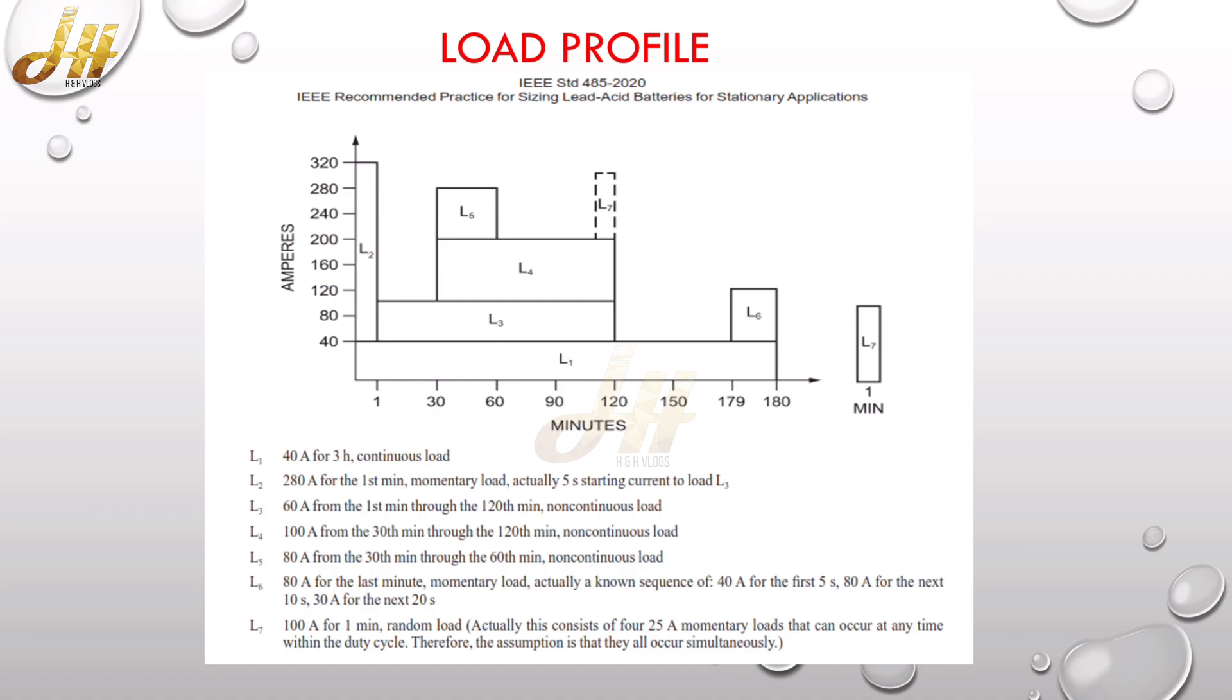L6 is 80 ampere, and another load which you are seeing is L7, which is a random load. This can occur at any point of time in this specific period cycle. Here they mentioned 100 ampere for one minute as the random load, so this will be calculated separately.